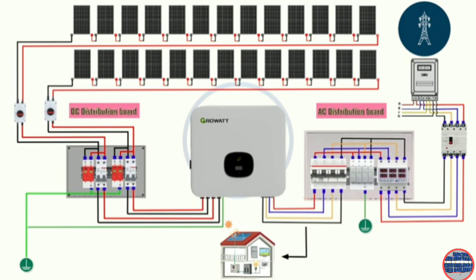Remember, each of these connections must be made securely and according to all local electrical codes. Use appropriately sized cables and ensure all connections are tightened to the correct torque specifications. After all connections are made, it's essential to test the system thoroughly. Verify the voltage at various points, check the operation of the voltage protection relay and SPD, and ensure the inverter is functioning correctly. And that's it. You've now successfully connected your 10 kW AC side grid-tied solar system. Again, I must emphasize the importance of hiring a qualified electrician for this work. Your safety is paramount.